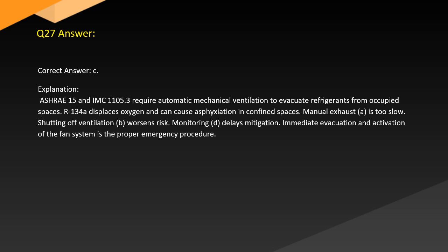Answer. Correct answer: C. Explanation. ASHRAE 15 and IMC 1105.3 require automatic mechanical ventilation to evacuate refrigerants from occupied spaces. R134a displaces oxygen and can cause asphyxiation in confined spaces. Manual exhaust, A, is too slow. Shutting off ventilation, B, worsens risk. Monitoring, D, delays mitigation. Immediate evacuation and activation of the fan system is the proper emergency procedure.